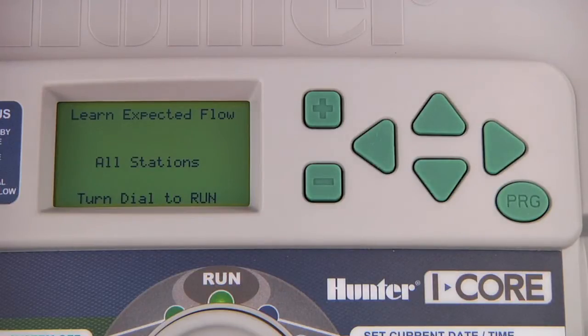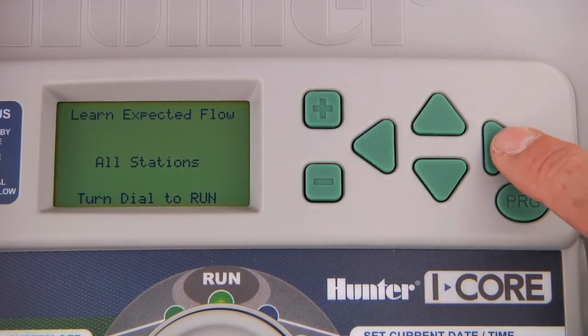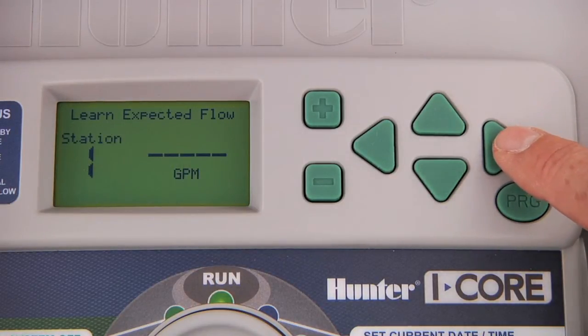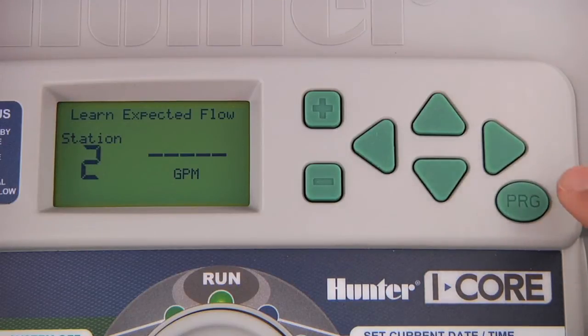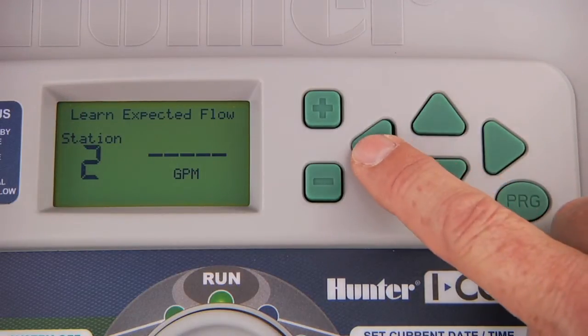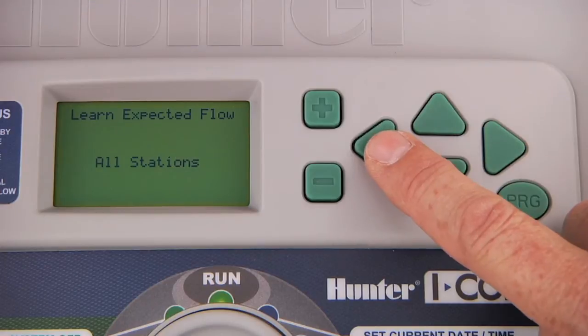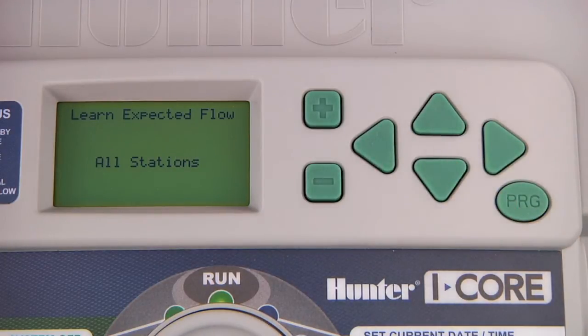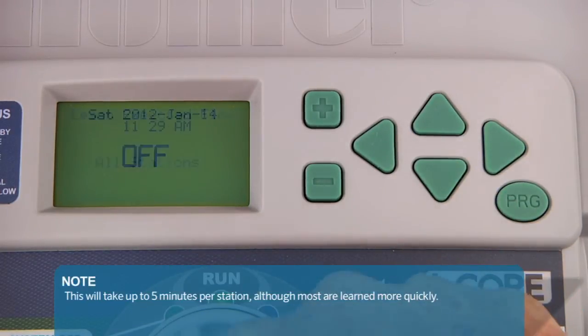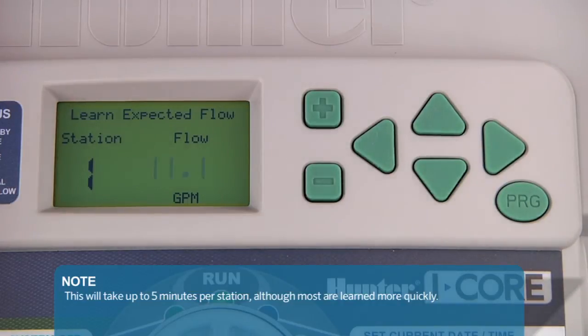You will be prompted to turn the dial to run if you want to learn all stations. If you only want to learn flow for a particular station, you can use the right arrow button to find the station you want to learn and then turn the dial to run. In our case, we want the controller to learn the expected flow for all the stations that we set to be monitored. Therefore, we simply turn the dial to run. The controller will start to activate each of the stations for a short period of time to learn the flow for each.